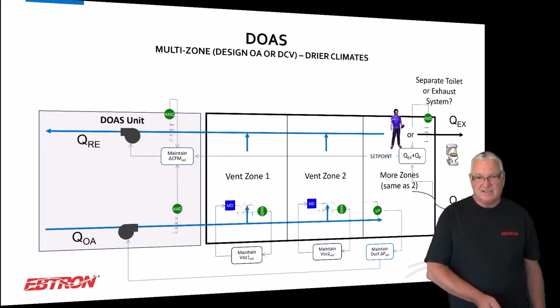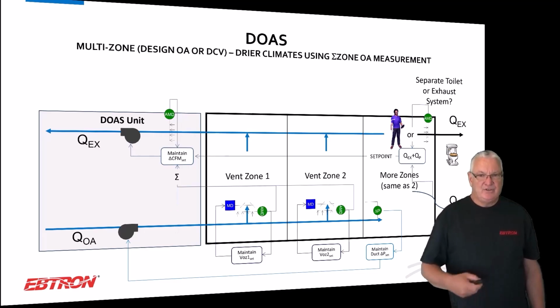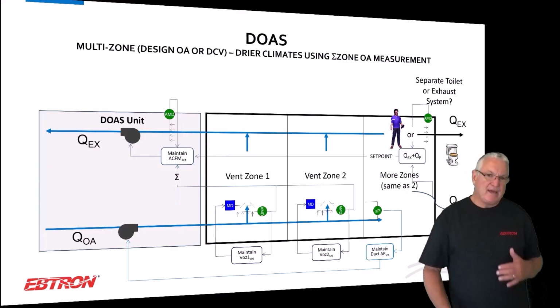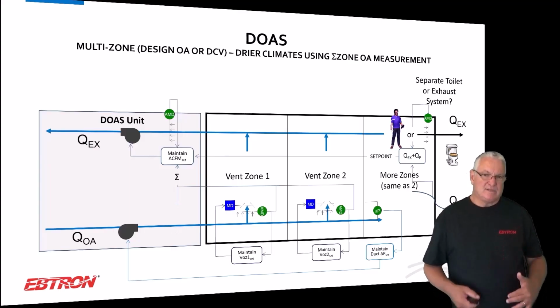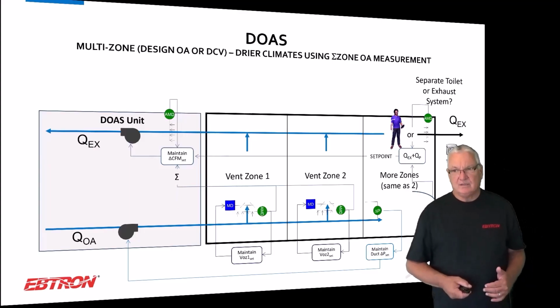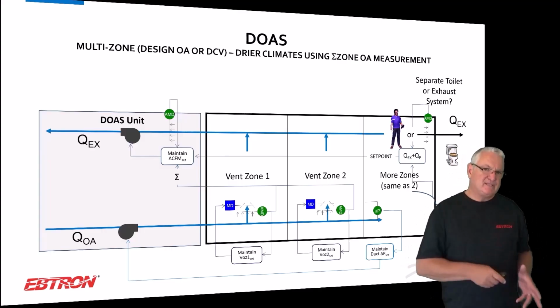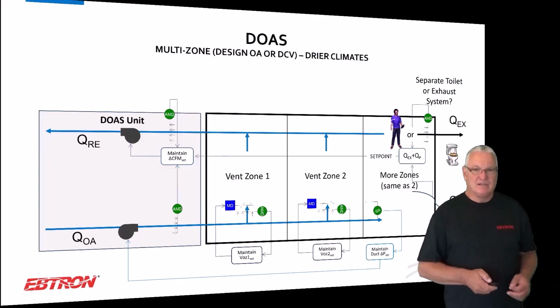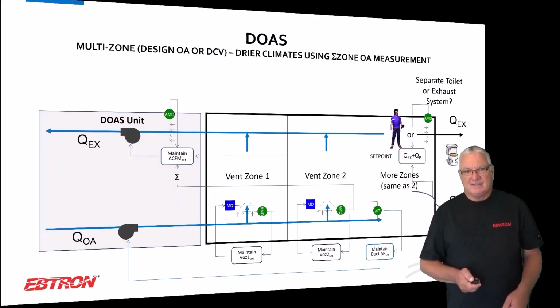Now, if you go here, notice I have flow measurement. I have some redundancy of flow measurement. This was the slide I was just on. I'm doing some redundancy of flow measurement on the supply side. The reality is, if you're using EBTRONs on the supply side, you can just sum them up. Okay, you don't have to do this. So it just depends on the equipment. Sometimes you're buying equipment and you want all the measurement to be in the piece of equipment, so that's this one. But if you're not, that's this one.